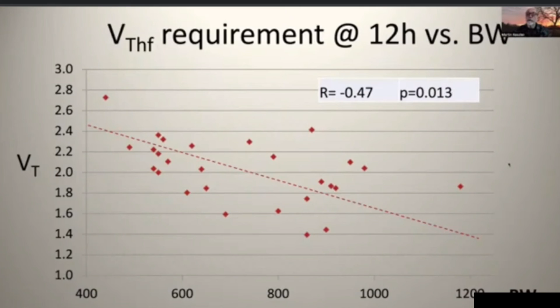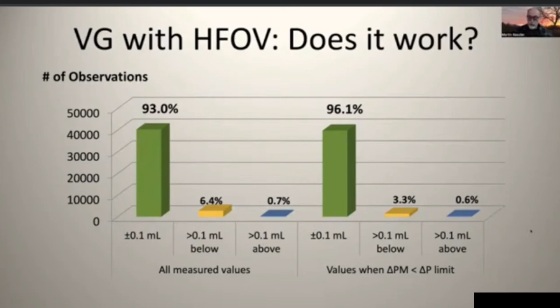And finally, I want to show you how reliably the tidal volume was actually met. So 93% of the time, the tidal volume that was measured was within 0.1 ml of the set tidal volume. A few times it was below. Some of those times it was because the pressure amplitude limit was not appropriately adjusted. So when we excluded those situations where it was user error limiting tidal volume delivery, the accuracy was 96%, which is really quite remarkable. Plus or minus 0.1 ml. So we found that the device really worked exactly as intended with very good reliability, ease of use. This was everybody's initial experience with the device, and yet there were very few significant problems. There were no safety concerns.